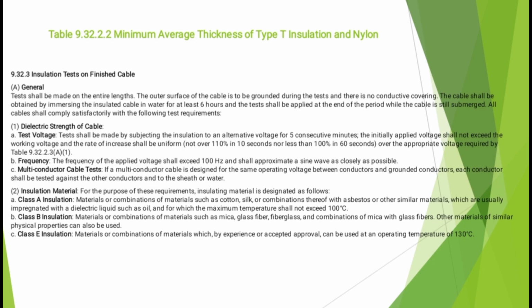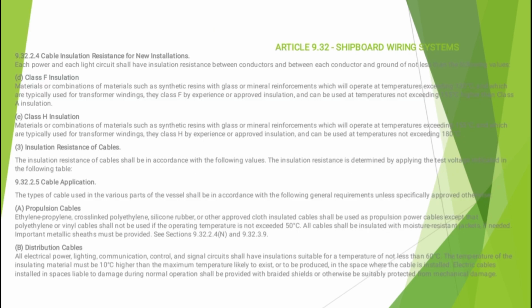Cable insulation testing outlines the procedures for testing the insulation of cables, including grounding, immersion in water, and applying specific voltage and frequency. Dielectric strength test describes how to test the dielectric strength of the cable insulation to ensure it can withstand high voltages. While insulation materials classification classifies insulation materials into Class A, Class B, and Class E based on their composition and maximum operating temperature. Cable insulation resistance for new installation: each power and light circuit must have a specific insulation resistance between conductors and between each conductor and ground.